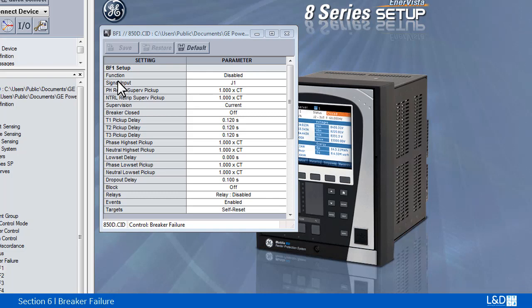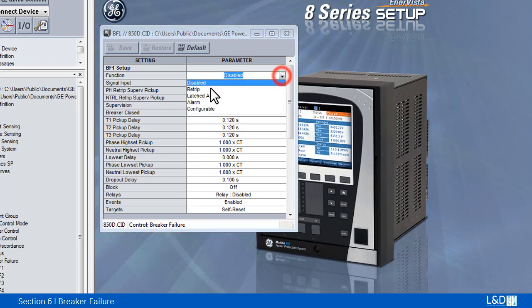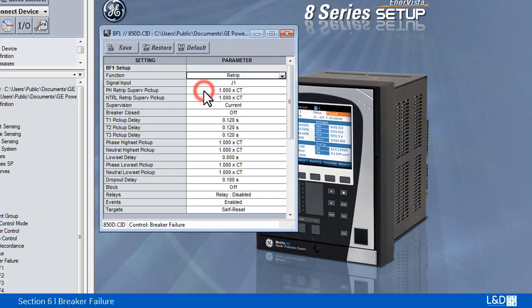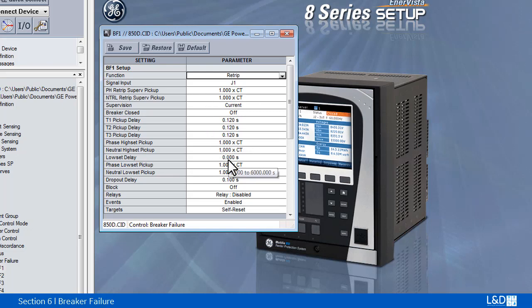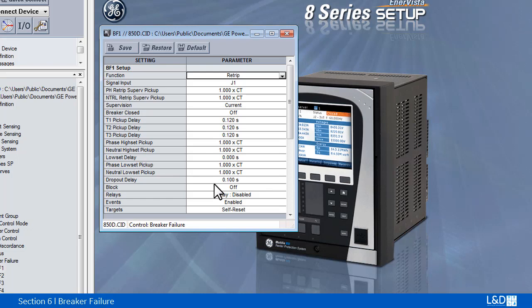When the function is set to re-trip, the scheme will be initiated by phase or neutral current higher than the re-trip supervision pickup. It immediately sends a trip signal to the breaker initially signaled to trip. In this way, it reduces the possibility of widespread tripping from a declaration of a failed breaker.